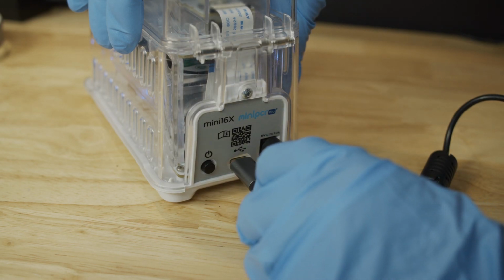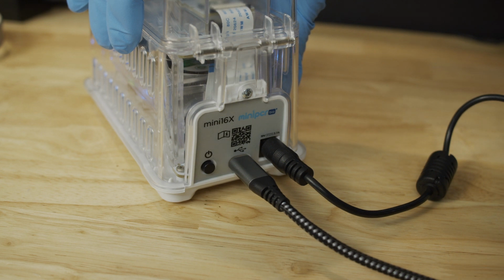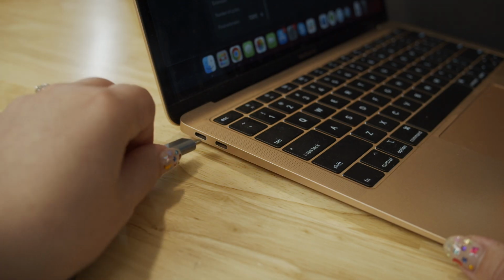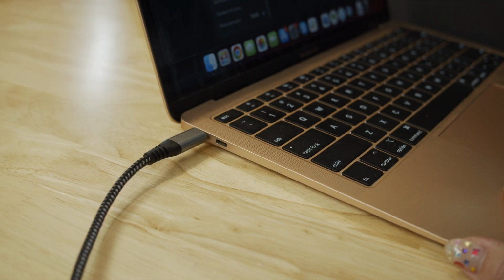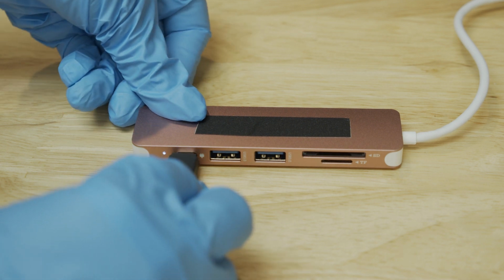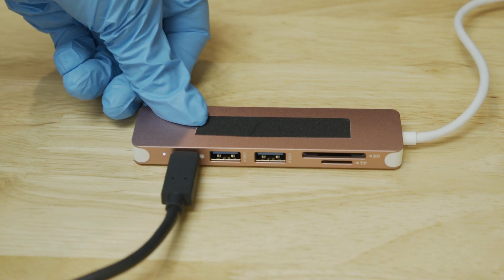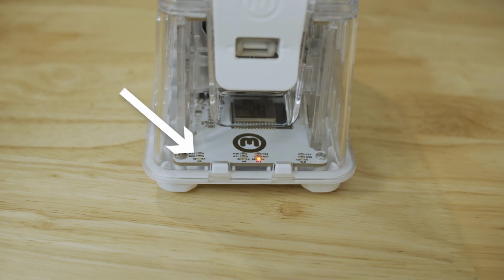Alternatively, to connect via USB, connect the USB-C cord to both the miniPCR and your device. An adapter can be used if your computer or mobile device does not have a USB-C port. Refer to the user's guide for detailed connection instructions using an adapter. When your miniPCR is successfully connected via USB, the blue LED will stop flashing and remain on. For more details, you can refer to the miniPCR user guide in the description below for connection troubleshooting.